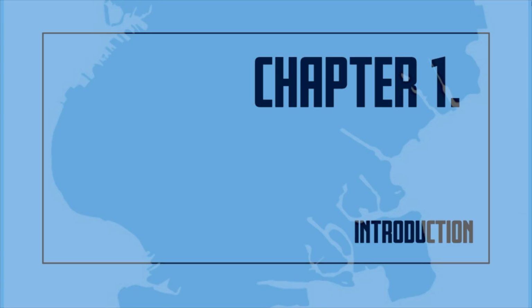Inspection, testing, servicing, and other maintenance of sprinkler systems must be personally supervised, Fire Code 901.6.3, and be performed in accordance with National Fire Protection Association Pamphlet No. 25, 2002 edition.